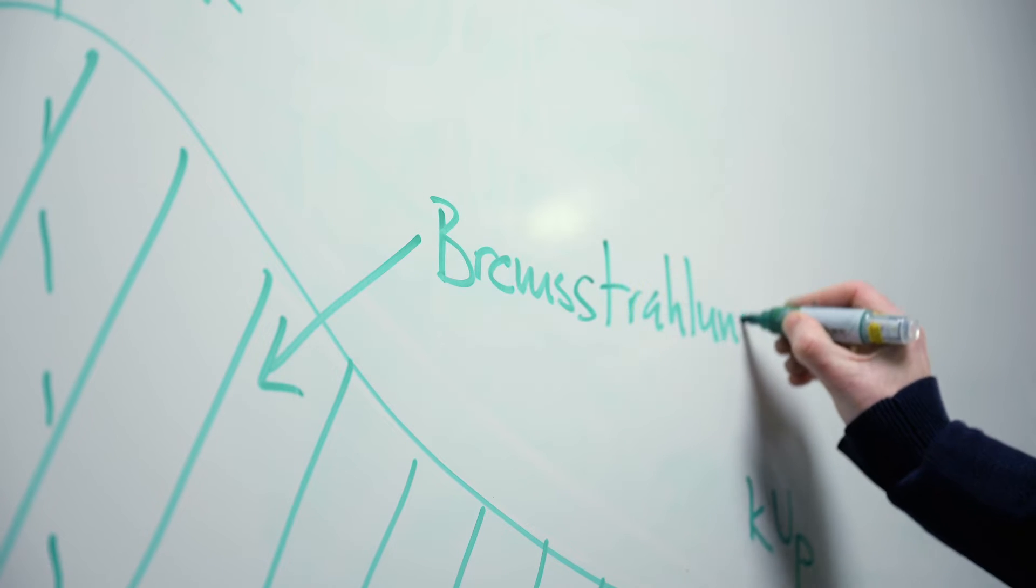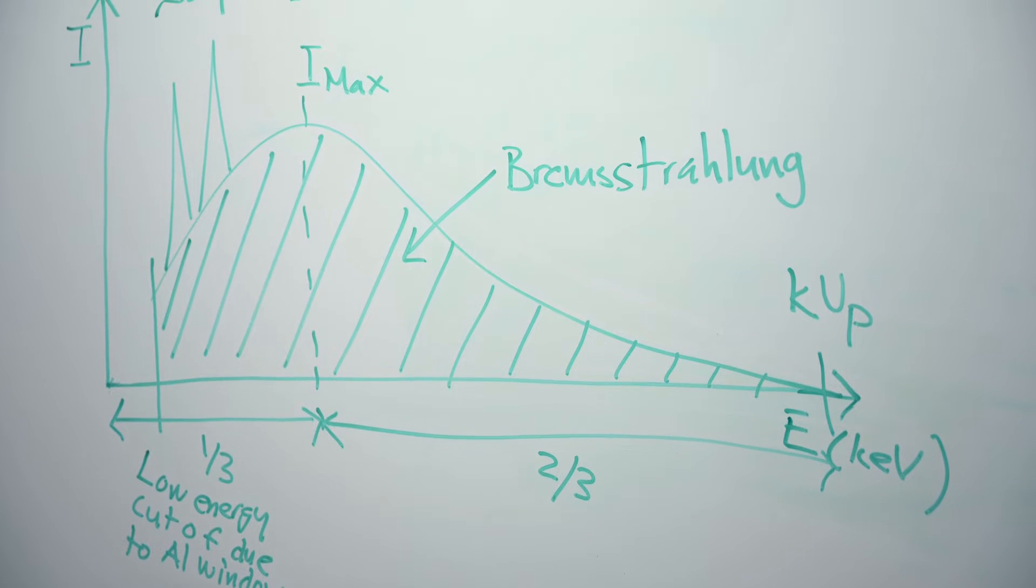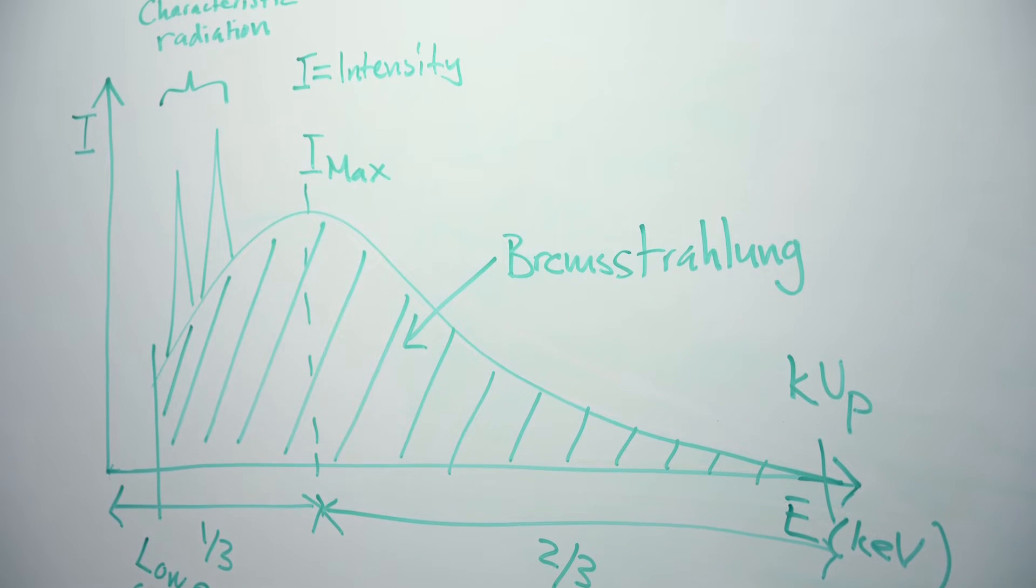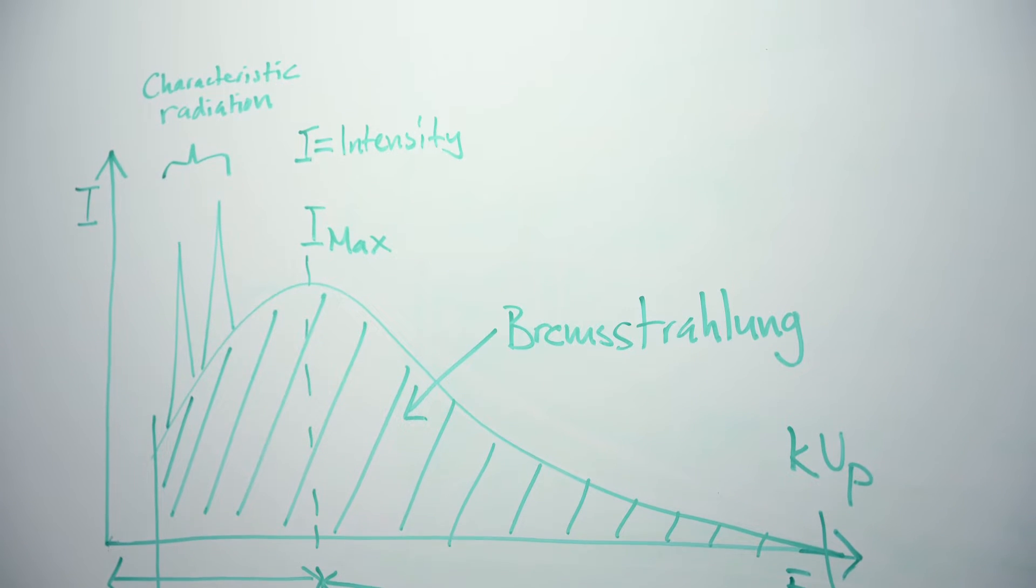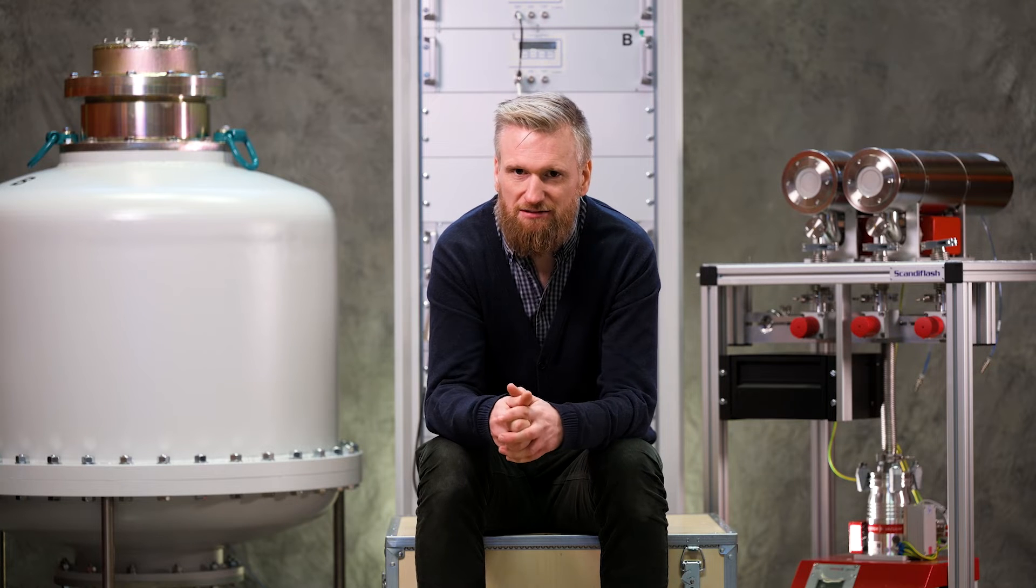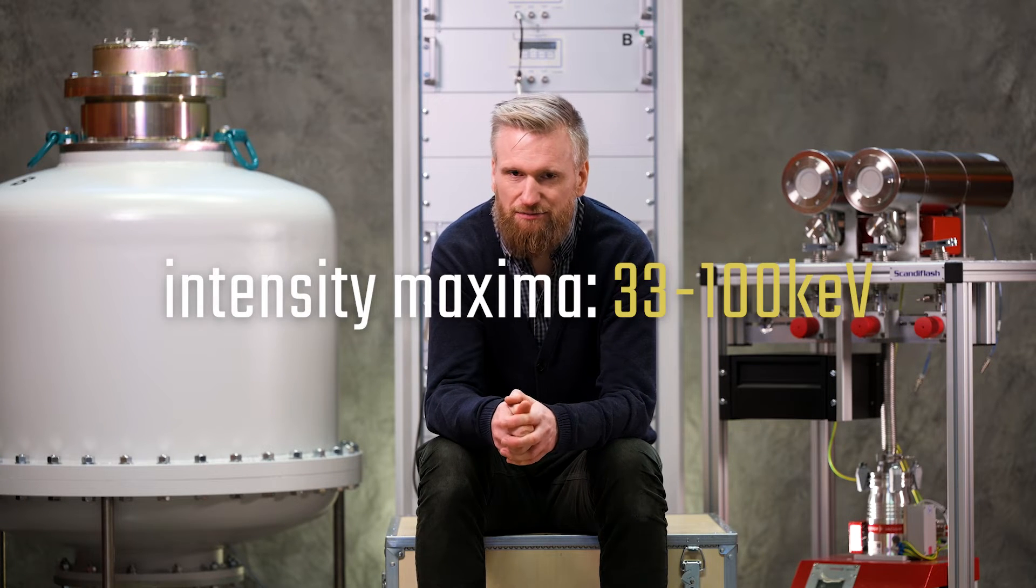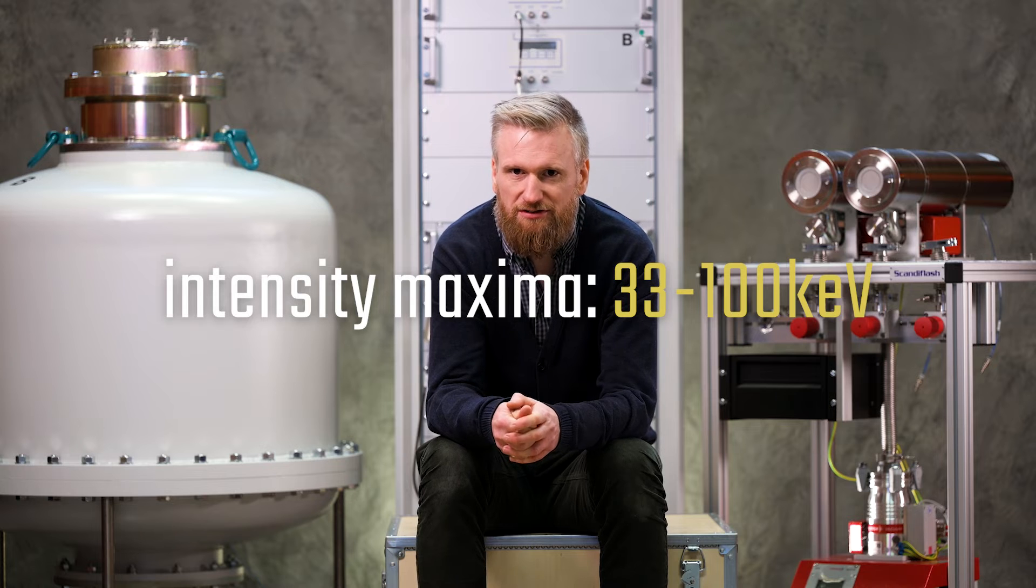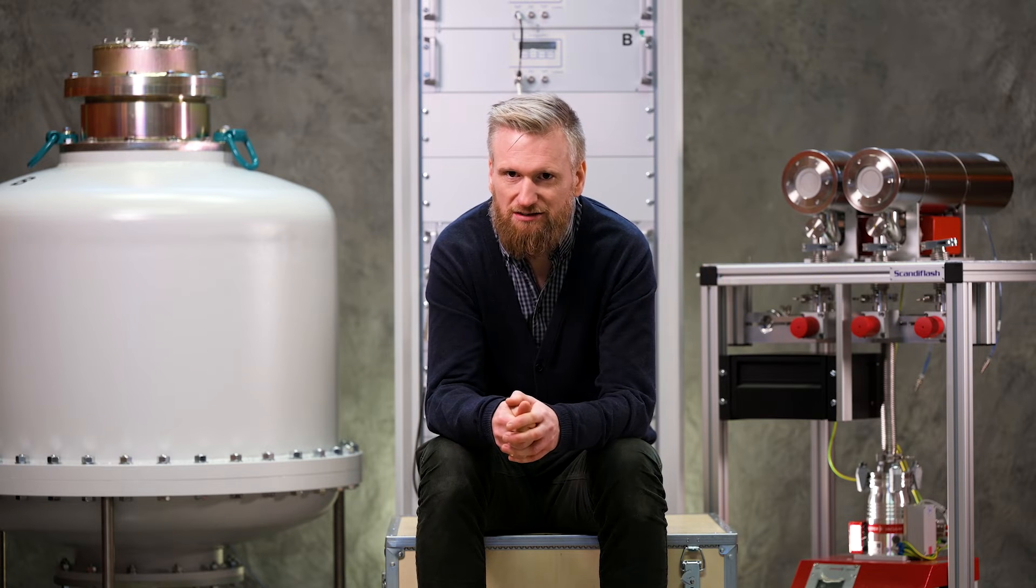So we are able to vary the energy output between 100 and 300 kVp. That means that we can fine-tune the intensity maxima to be in the order of 33 to 100 keV. And that's ideal for capturing objects contained in aluminum, for example.